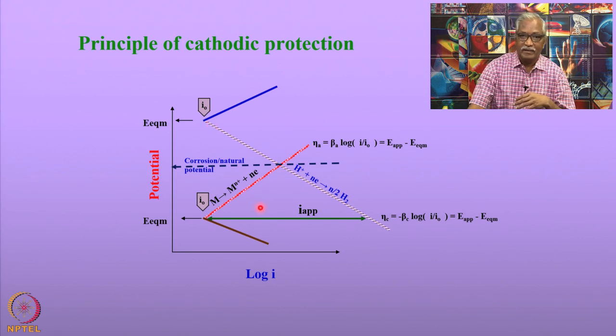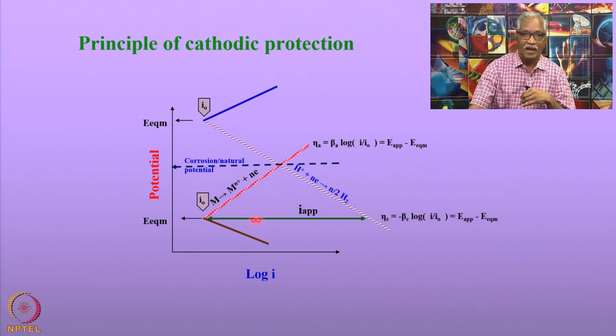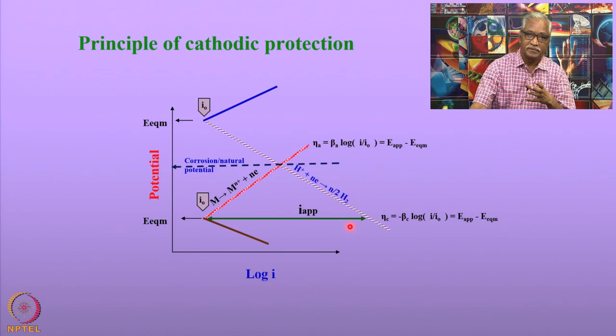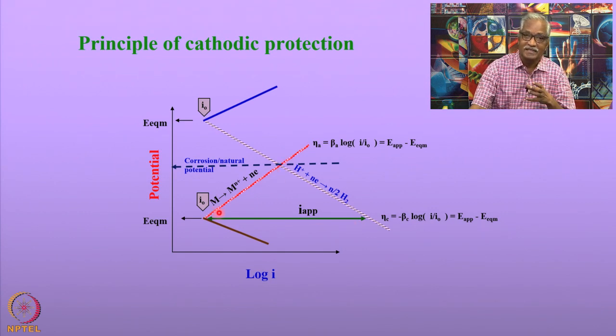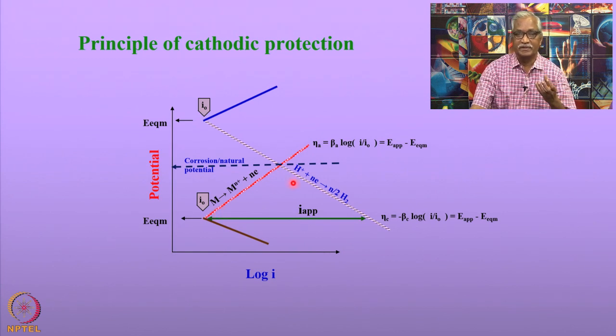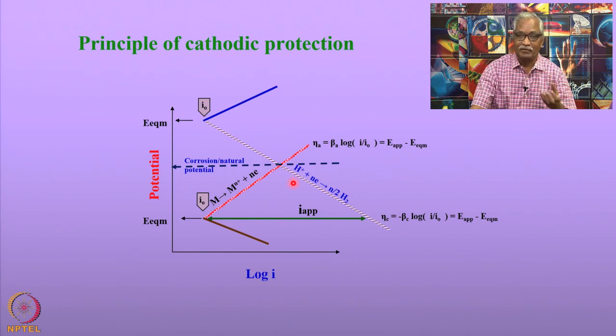The corrosion current density and corrosion potential are governed by parameters such as exchange current density for the cathodic reaction, exchange current density for the anodic reaction, and the Tafel relationships for both the anodic reaction — metal oxidation — and the cathodic reaction — reduction of species such as oxygen or H⁺ ions on the metallic surface. Depending upon the slope of either reaction, the current required for cathodic protection changes, and this slope also decides whether the applied potential is adequate to protect the metal to the desired levels.